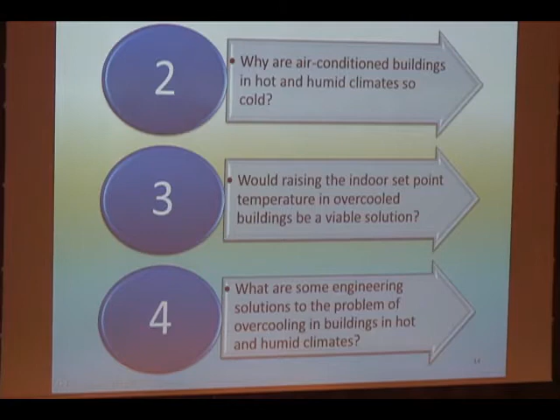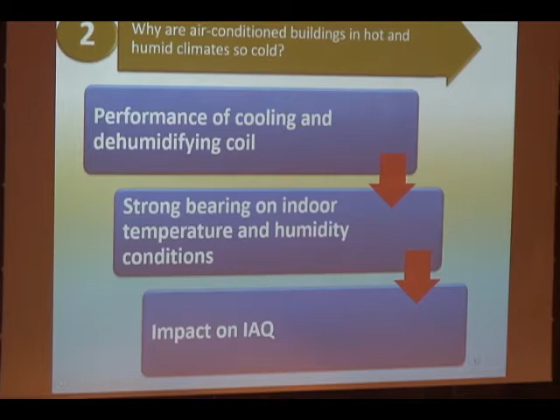One reason buildings are overcooled is the mismatch between what happens at the air handling unit, what the air conditioning system has to do, and what we actually experience as demand in the space. The role of the cooling coil is critical here. The cooling and dehumidifying coil has a demanding job removing heat, both sensible heat and latent heat.